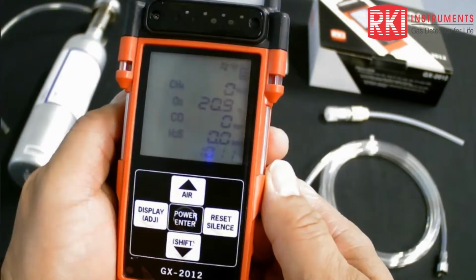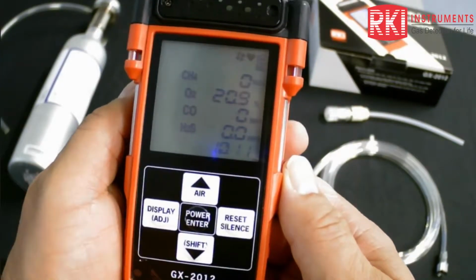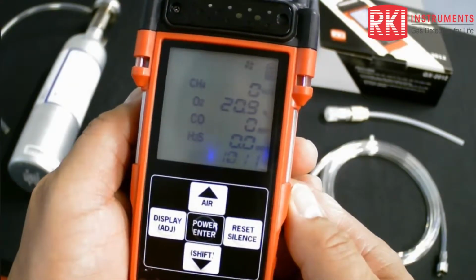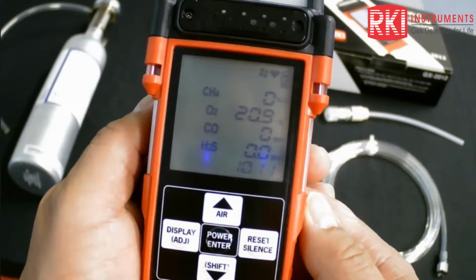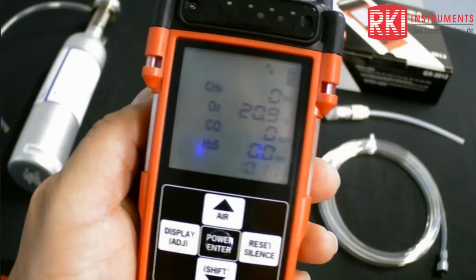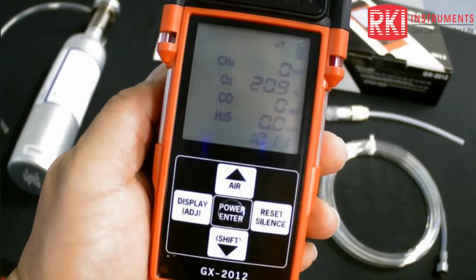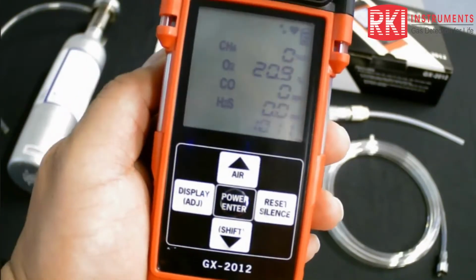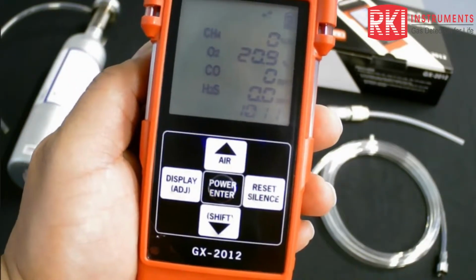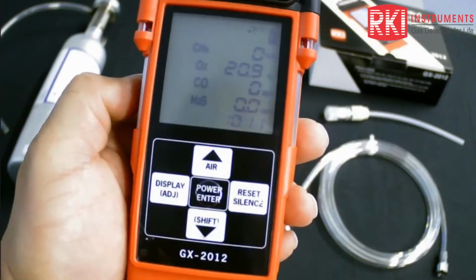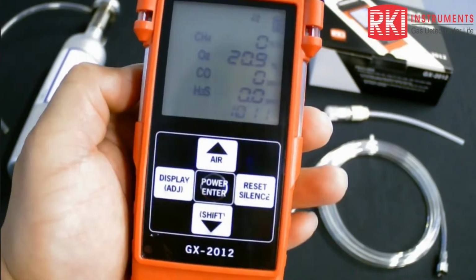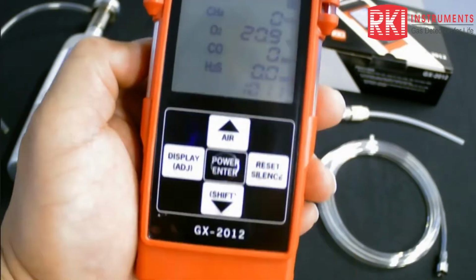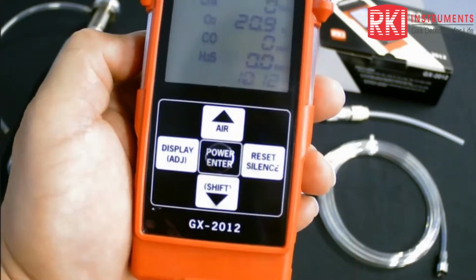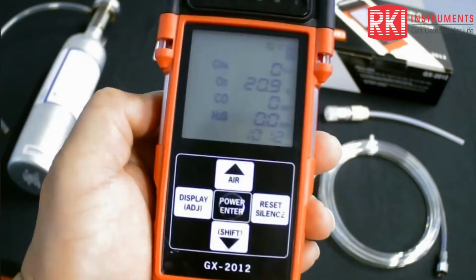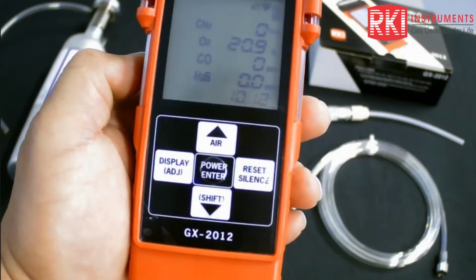Okay, so here we've got the display of the unit, and this is the standard 4-gas configuration that we're looking at, obviously. And it's really typically what you would see, even if you had 5 sensors in your unit, which I do, as well as you there in front of you, you mentioned. So what we see on the display is methane, CH4, oxygen O2, CO, carbon monoxide, H2S, hydrogen sulfide. So for the standard LEL range, the lower explosive limit, it's basically methane in this case. We are looking at a 0 to 100% LEL range. So basically your scale is broken up into 100 units from 1% LEL, 2% LEL, all the way up to 100% LEL. And the lower explosive limit, the LEL for methane, is 5% by volume of methane, okay?